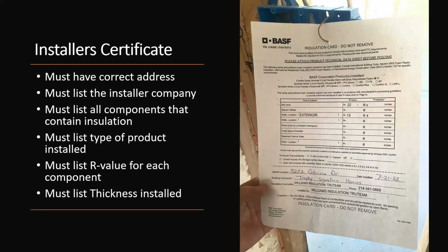And we've talked about this a second ago, but if you're having insulation in the walls that no longer have R values, so you've got foam, you've got cellulose, you've got blown fiberglass wall insulation, the code now allows you to call out and say, I need a certificate posted before sheetrock, immediately after the installation, that shows me what you've installed and that it meets compliance of the energy code. But if you look at this, it's a 2x4 wall. They actually put the exterior wall was 4 inches. We know by construction that that is not true. And if they're saying they're getting an R15 with foam because it's 4 inches deep, you are a half inch short of that because the framing is not 4 inches deep. It's 3.5. So if you do the math, it is not R15, but that's what the energy model was built with, showing compliance for the energy code as 15, but yet it's probably not.